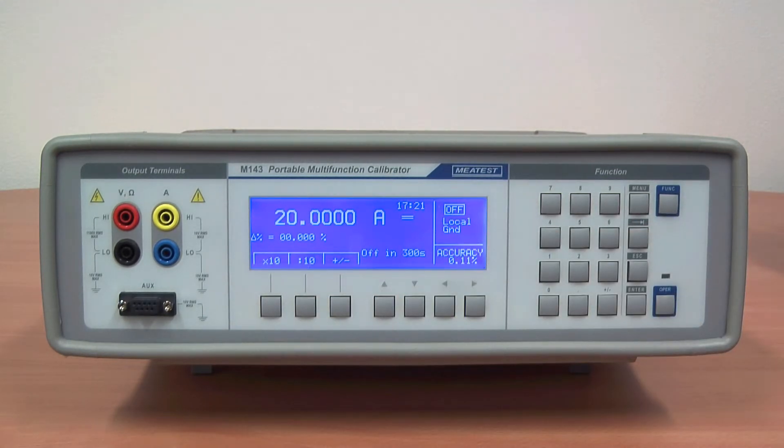Portable simulator obviously can't generate 20A all day long, so when you select value higher than 10A, a small timer with maximum output time will appear. Still, the M143 can generate up to 10A continuously and time limit at 20A is full 5 minutes.